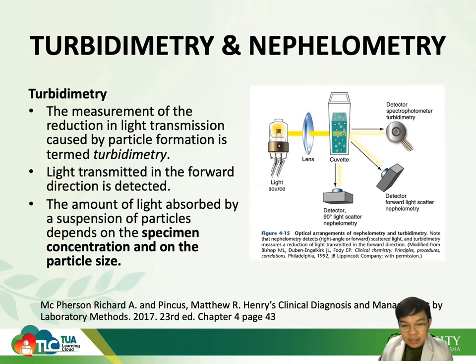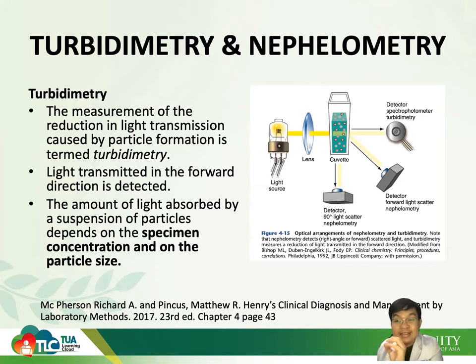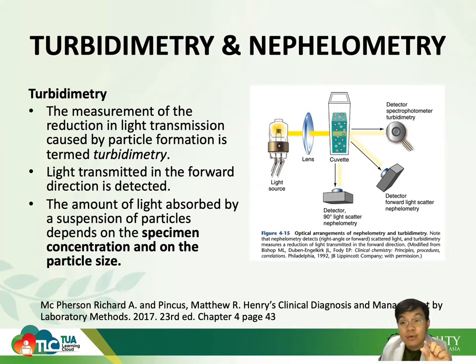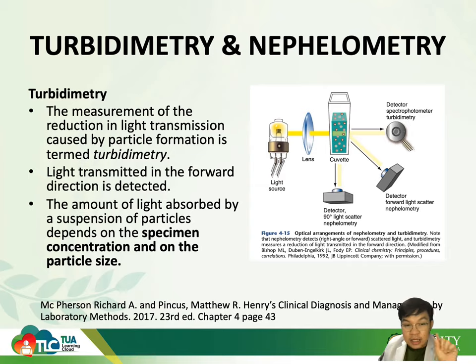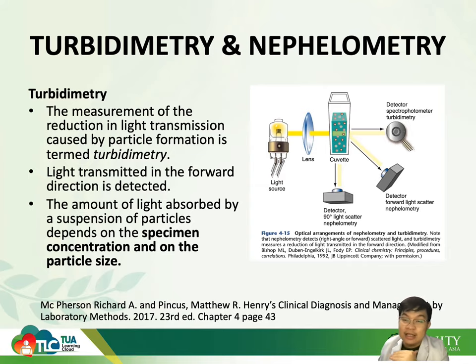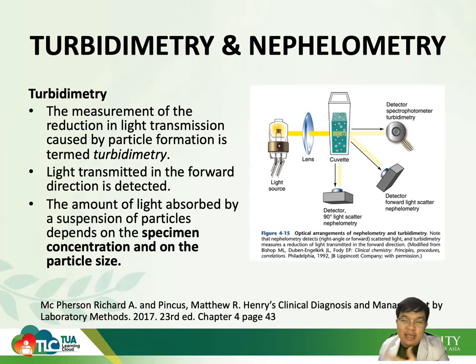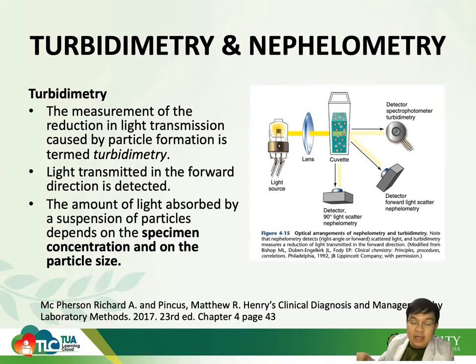In contrast, in turbidimetry, we measure the reduction of light transmission — how much light is being blocked or covered by your antigen-antibody complex or other proteins. Looking at the illustration from the light source, you have the lens, the cuvette, and then after the cuvette, the detector — similar to the spectrophotometer, and also your turbidimetry. The orientation of the components is similar to your spectrophotometer. The light transmitted in the forward direction is the one being detected — we're not measuring light scattered at any angle, just measuring linearly at 180 degrees.